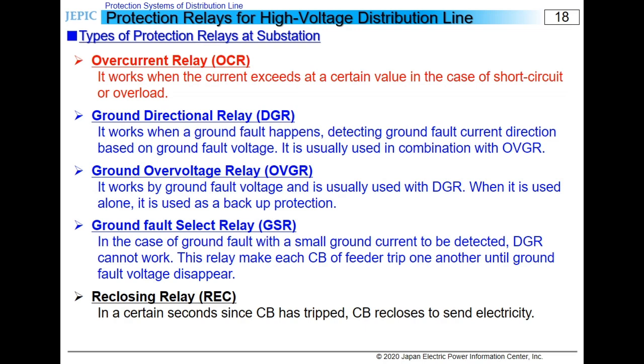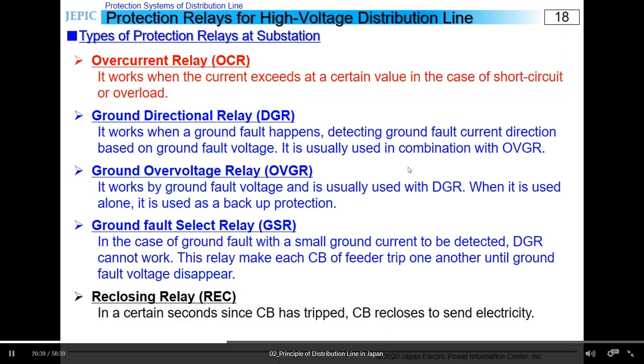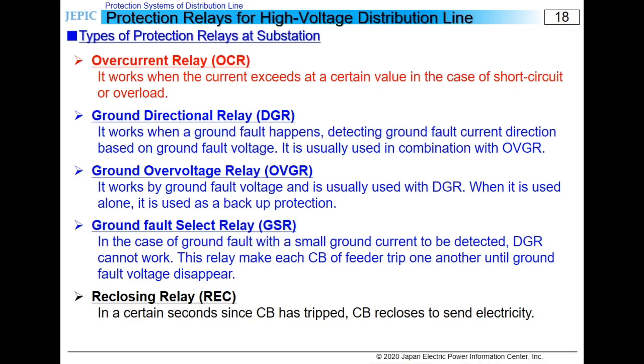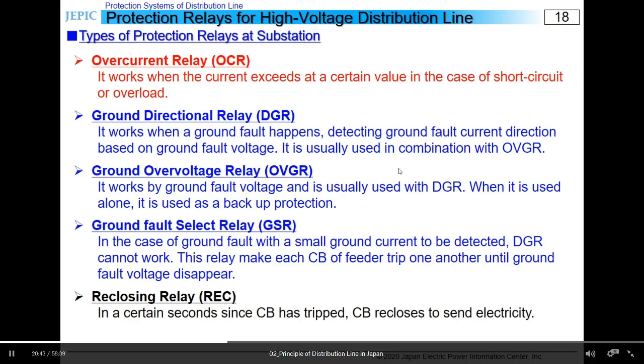This is because overcurrent is a phenomenon that always involves two phases or more, so monitoring only two phases is enough to detect overcurrent. Since overcurrent might cause conductor melting or damage on equipment, its work time to trip CB is set shorter than that of ground fault relays, and distribution line equipment are designed to bear a fixed short circuit current, and distribution line is also designed not to exceed the fixed value.